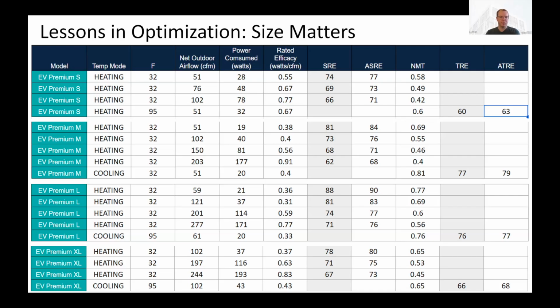For that same 102, we could just use the 121 CFM in the Premium L. So even more airflow, but we see that the wattage is 37, less than half the watts used, and it's also 12% higher, from 71 to 83% apparent sensible recovery efficiency. I know there are a lot of numbers on this and it might be tricky to follow, but I think the main takeaway is that smaller systems, for the same airflow, are going to use more power and have lower recovery efficiencies. Larger systems are going to be more efficient, run slower, and have higher recovery efficiencies.